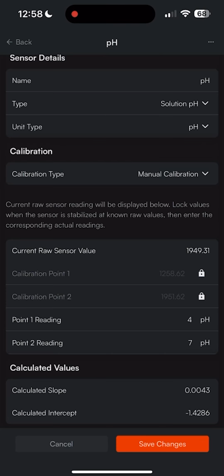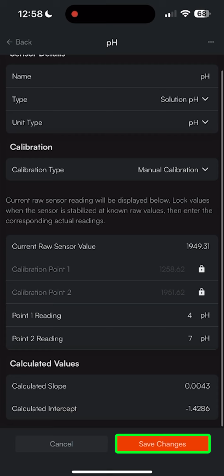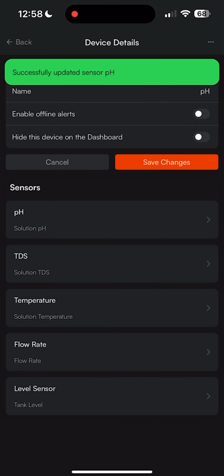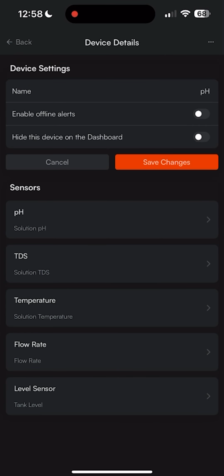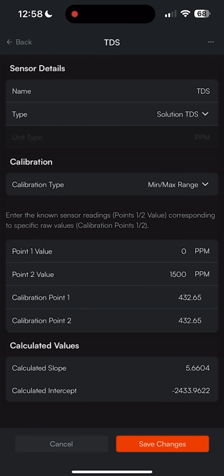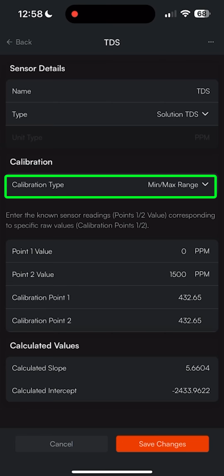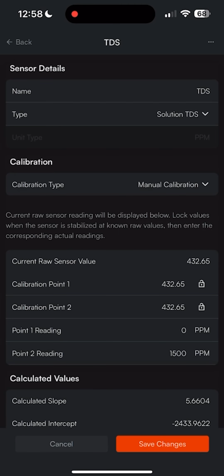and then all that is left is to save these changes, as we've already made an equation that's mapping the sensor readings to two specific calibration standards. Next, for the TDS port, we'd also make a similar manual calibration. We'll start by tapping the TDS input, and then changing the calibration type from min-max range to a manual calibration.